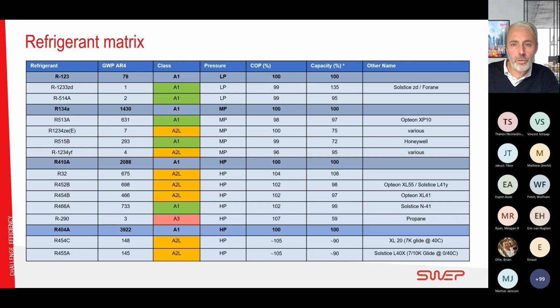And when you use this table, you should know that they're grouped. So for example, in the case of 134A, we have set 100% for these, and that is in relation to the 4 different refrigerants below. So in the case of ze(E), we can see that we have the same COP for a reference case, but we will have 25% less cooling capacity than 134A.